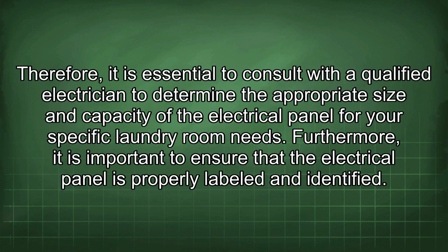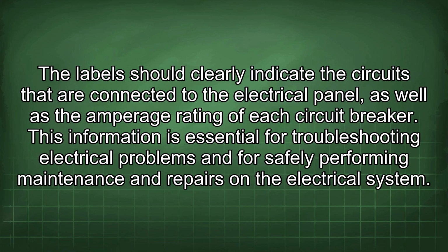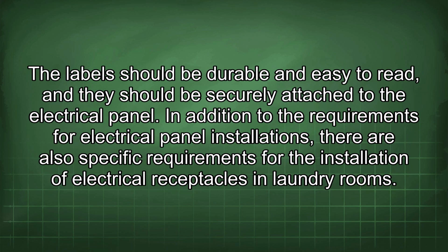Furthermore, it is important to ensure that the electrical panel is properly labeled and identified. The label should clearly indicate the circuits that are connected to the electrical panel, as well as the amperage rating of each circuit breaker. This information is essential for troubleshooting electrical problems and for safely performing maintenance and repairs on the electrical system. The label should be durable and easy to read, and it should be securely attached to the electrical panel. In addition to the requirements for electrical panel installations, there are also specific requirements for the installation of electrical receptacles in laundry rooms.